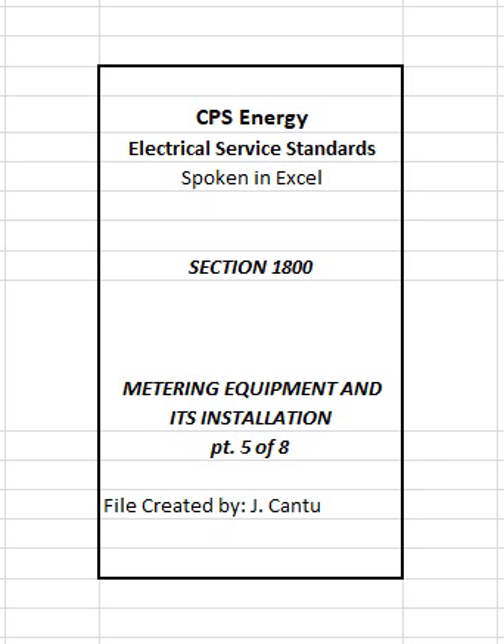1807.3 Headroom clearance at meters. Headroom above final grade or floor level shall not be less than 6 feet 6 inches or the height of metering equipment including the minimum spacing clearances outlined in Article 1807(2) of this section. Enclosure covers must be readily removable for complete exposure of internal equipment without being blocked by ceilings or overhead objects.